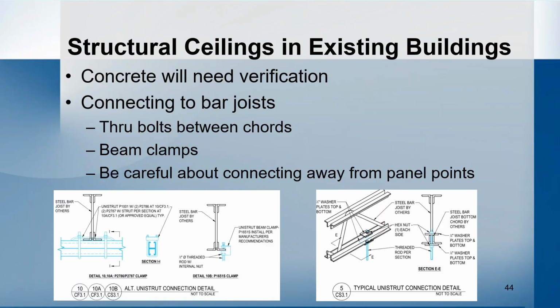So for that existing building condition, if it's concrete, then you'll need to verify the capacity of the concrete. Typically, you'll have to get a manufacturer out there to do some pull tests for some of your connections, just to ensure that the connection you're designing is actually sufficient. For bar joists, there are a number of ways that you can connect, similar to typical steel connections. Alternatively, you can use through bolts between the chords, or beam clamps. One thing you need to be careful of, and we also see bar joists in new construction, is the panel point connections. Typically it's somewhere between 1 foot to 6 foot within a panel point that you need to make those connections, so that can present some coordination issues that you just need to be careful of.